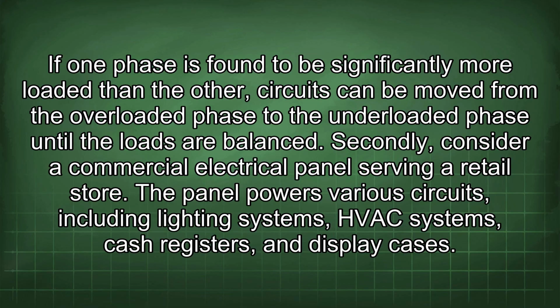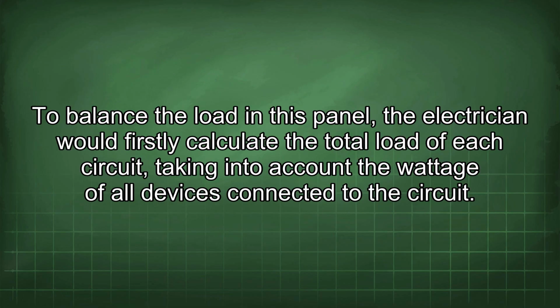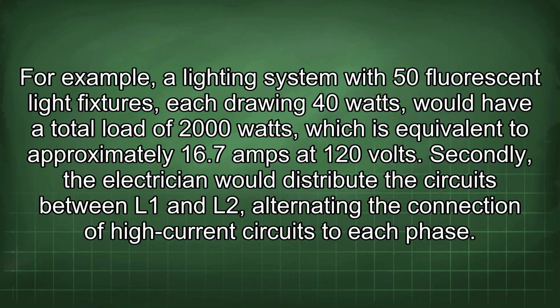Secondly, consider a commercial electrical panel serving a retail store. The panel powers various circuits, including lighting systems, HVAC systems, cash registers, and display cases. To balance the load in this panel, the electrician would firstly calculate the total load of each circuit, taking into account the wattage of all devices connected to the circuit. For example, a lighting system with 50 fluorescent light fixtures, each drawing 40 watts, would have a total load of 2000 watts, which is equivalent to approximately 16.7 amps at 120 volts.